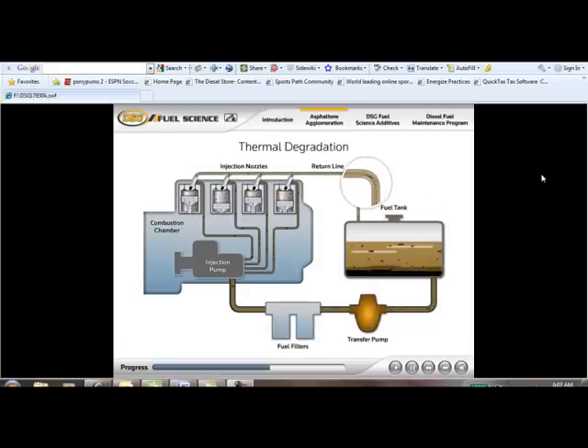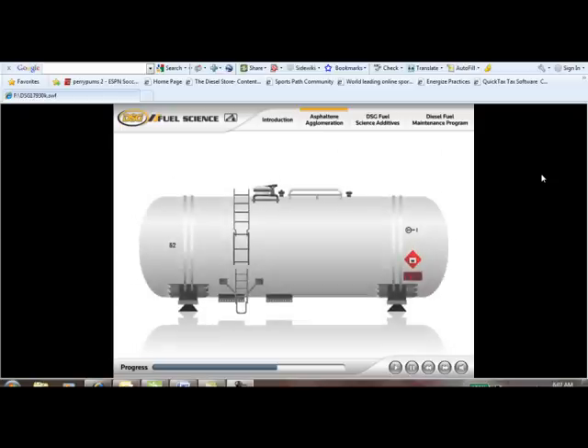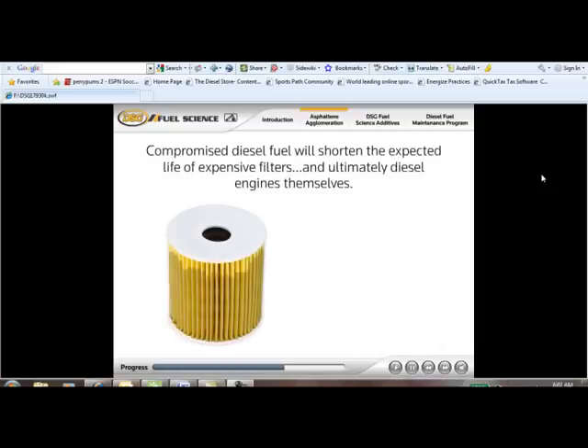These stubborn deposits contaminate the fuel system via return line heating, causing premature filter plugging that some call black filter syndrome, leading to more frequent repairs, poor performance, higher fuel consumption, and higher maintenance costs. In cold weather, fuels with higher paraffin content can congeal into wax crystals that, along with ice from condensation, can plug fuel filters.